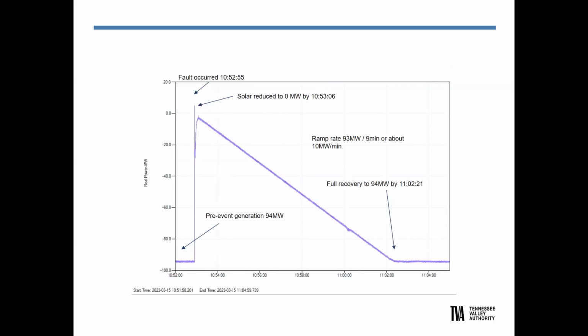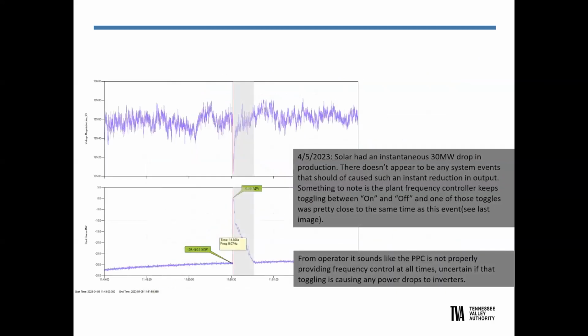So again, about 94 megawatts pre-event. The fault occurred. You can see it drops to nearly zero, and it takes a very long time to climb back out of it. If you go to the next slide, you can see the PMU and the DFR shots here of the reactive as it ramps back up, and then you can see the voltage swings there at the local site as it recovers. From the operator, they said it sounded like the PPC is not properly providing frequency control, and it could be causing power to drop to the inverters.